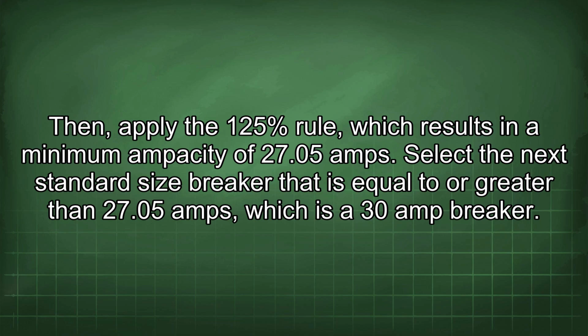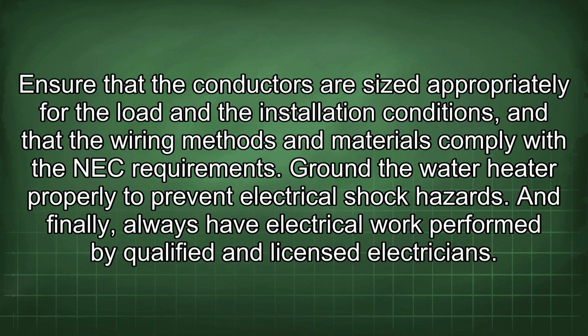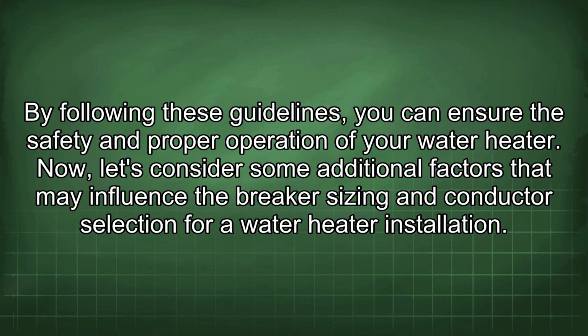Select the next standard size breaker that is equal to or greater than 27.05 amps, which is a 30 amp breaker. Ensure that the conductors are sized appropriately for the load and the installation conditions, and that the wiring methods and materials comply with the NEC requirement. Ground the water heater properly to prevent electrical shock hazards. And finally, always have electrical work performed by qualified and licensed electricians. By following these guidelines, you can ensure the safety and proper operation of your water heater.